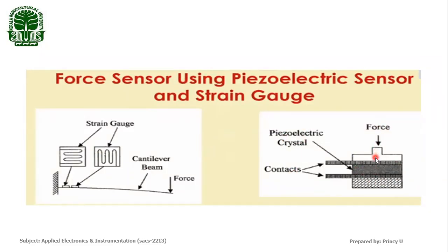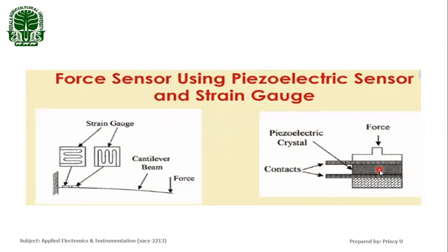When we apply a force to be measured, a piezoelectric crystal is placed on a diaphragm. The force applied on this material produces a charge on the piezoelectric crystal. The charges accumulate on the contacts, and when we take an output through these contacts, we get an output voltage proportional to the deformation of the piezoelectric material — and thus proportional to the applied force.